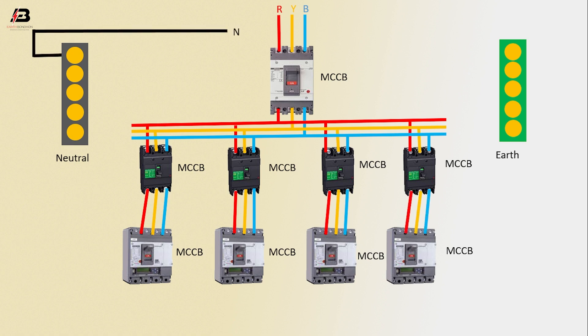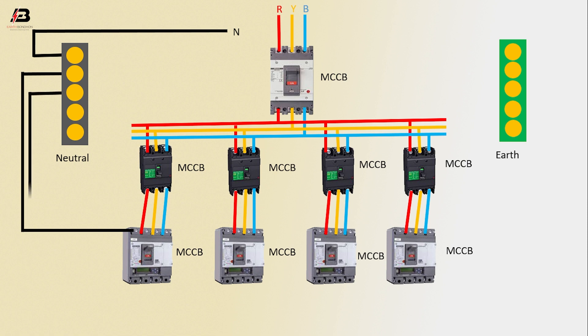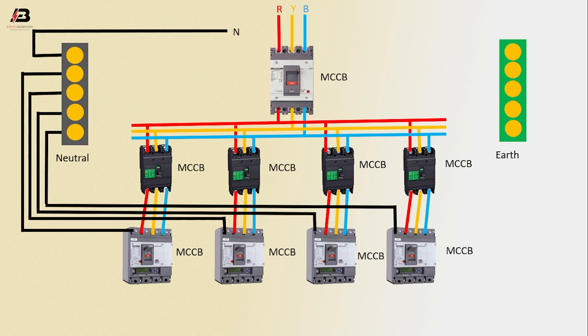Neutral connection input to neutral bus bar. Output connection neutral from neutral bus bar to connect MCCB. Another output connection to another MCCB, again another MCCB, and again another MCCB neutral connection. Earthing connection input to earthing bar.